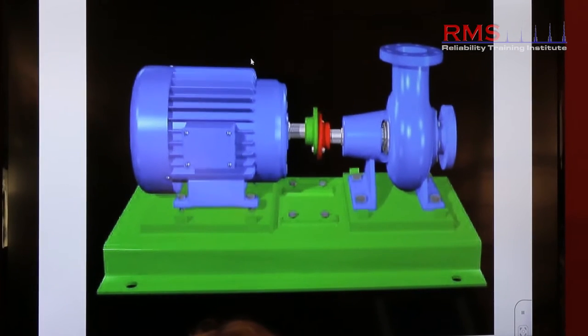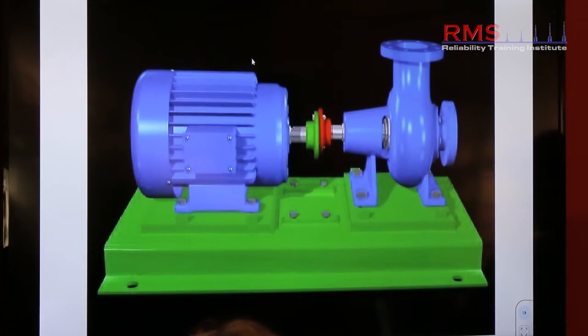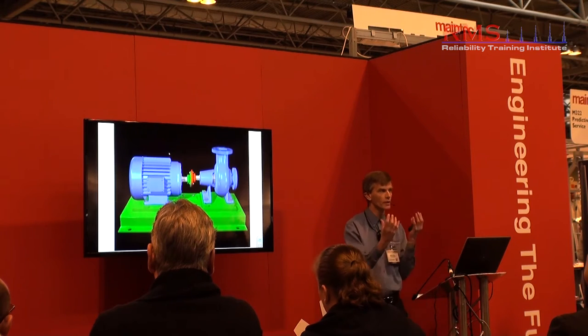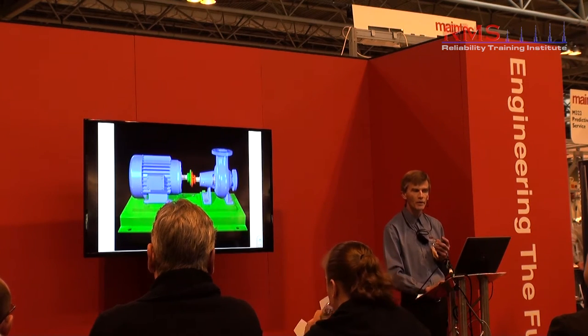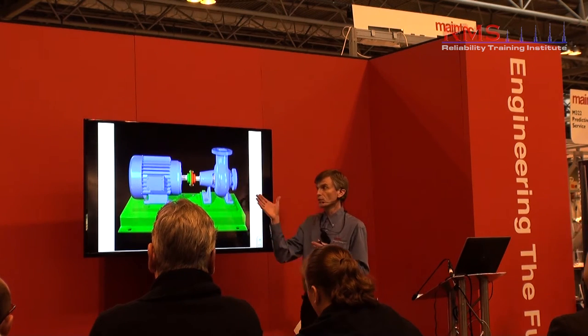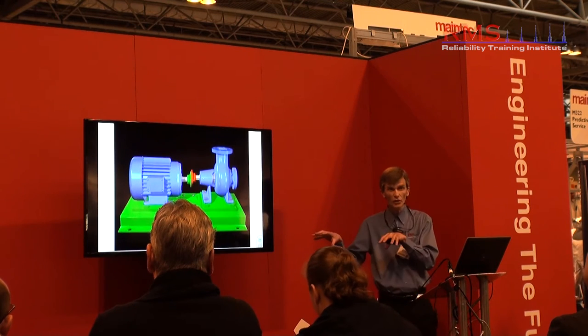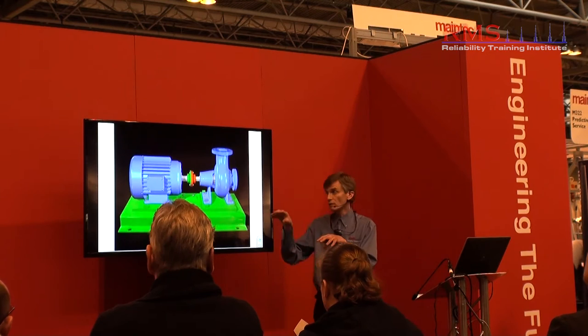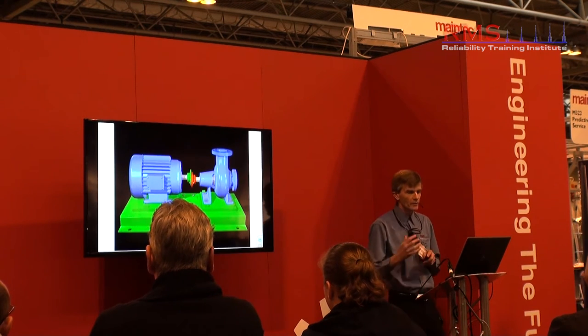A key point to think about with vibration is the forces. Think of the forces. The forces here are radially being generated. If I place a sensor radially around this machine, I will measure those forces. Obviously very exaggerated, but if the machine were misaligned like this and it was bolted down, that machine is trying to do this in real operation, and that's going to destroy the shaft bearings, the shaft seals, and so forth.